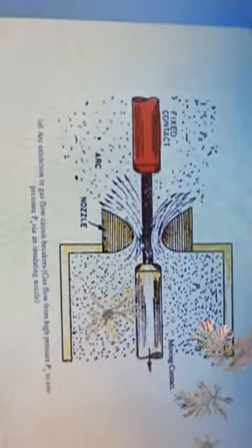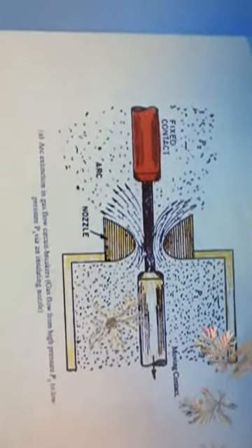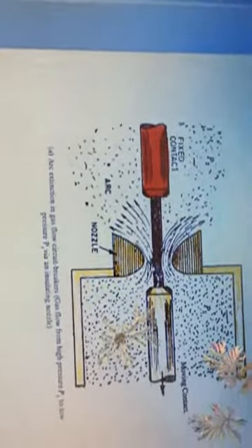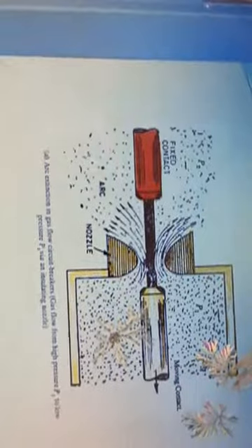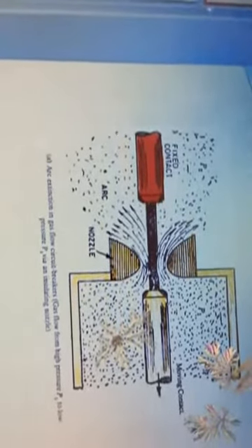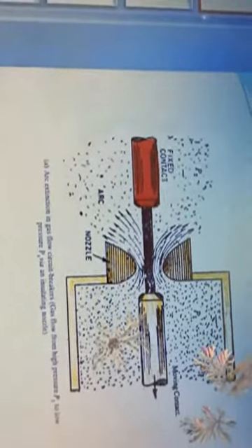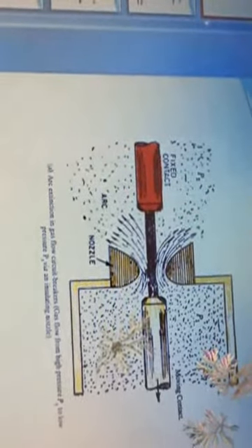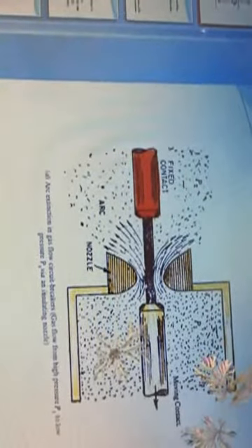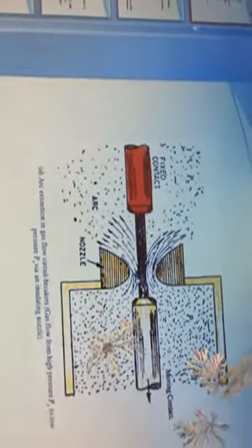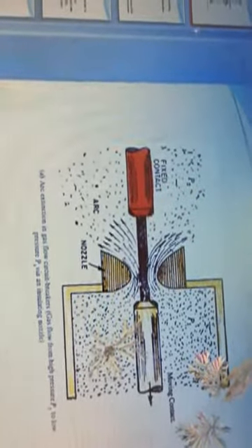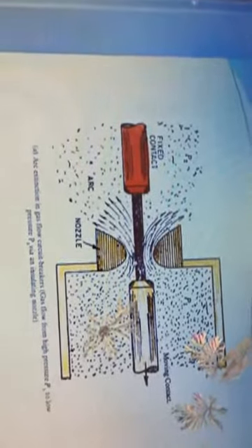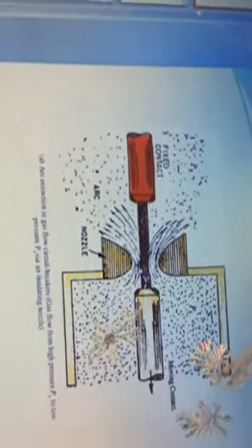The arc extinction process of SF6 gas is different from that of the air blast circuit breaker. During the arcing period, SF6 gas is blown axially along the arc. The gas removes heat from the arc by axial convection and radial dissipation. So the arc diameter reduces during the decreasing mode of the current wave. The diameter becomes small at current zero, and turbulent flow is introduced around current zero to extinguish the arc.